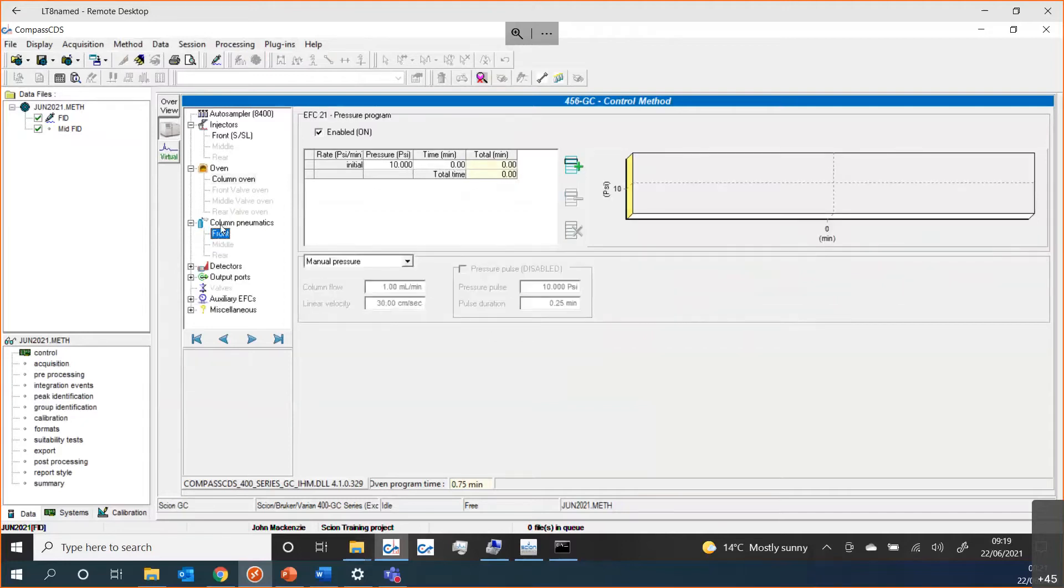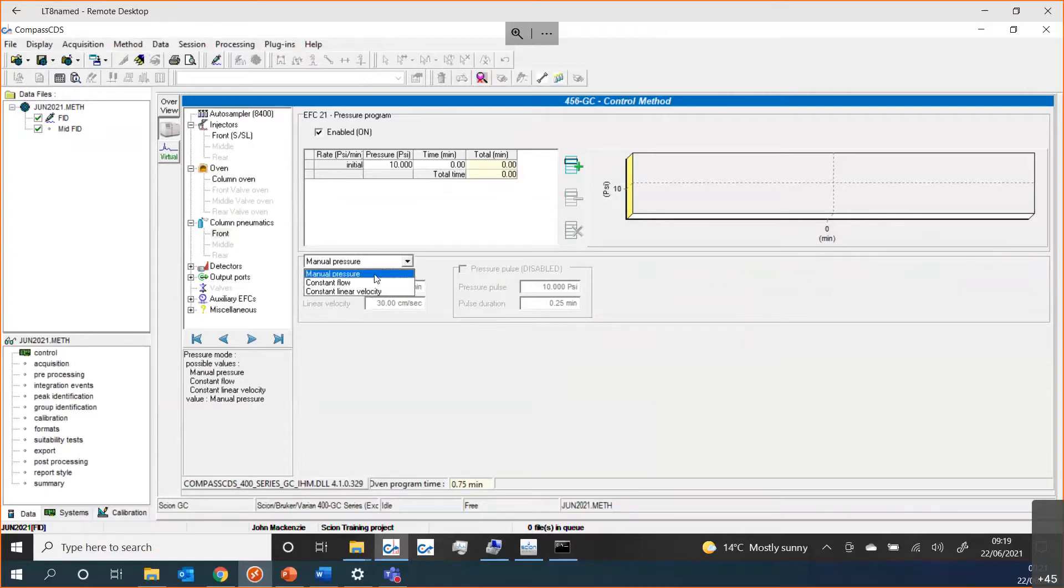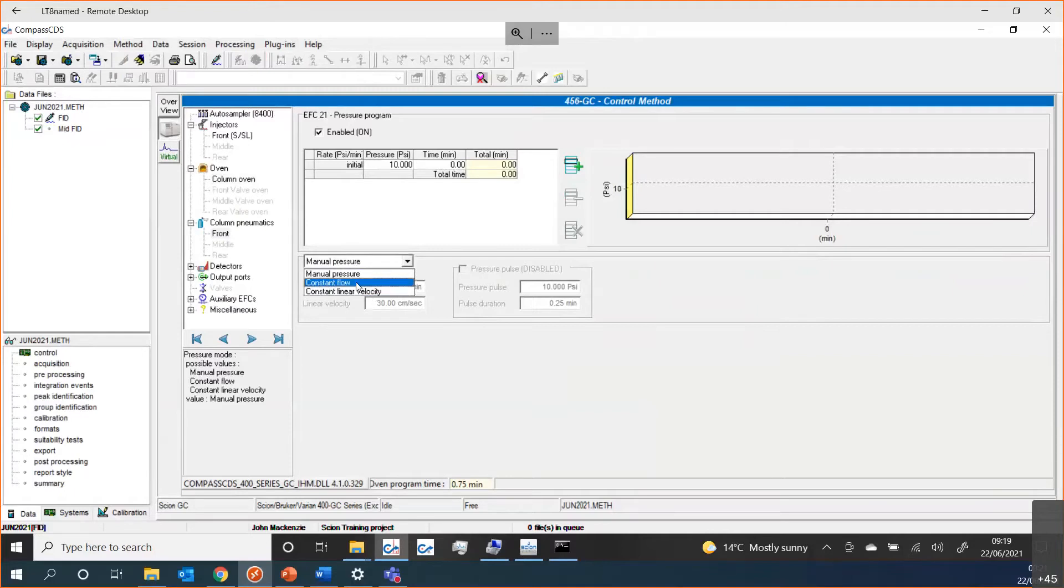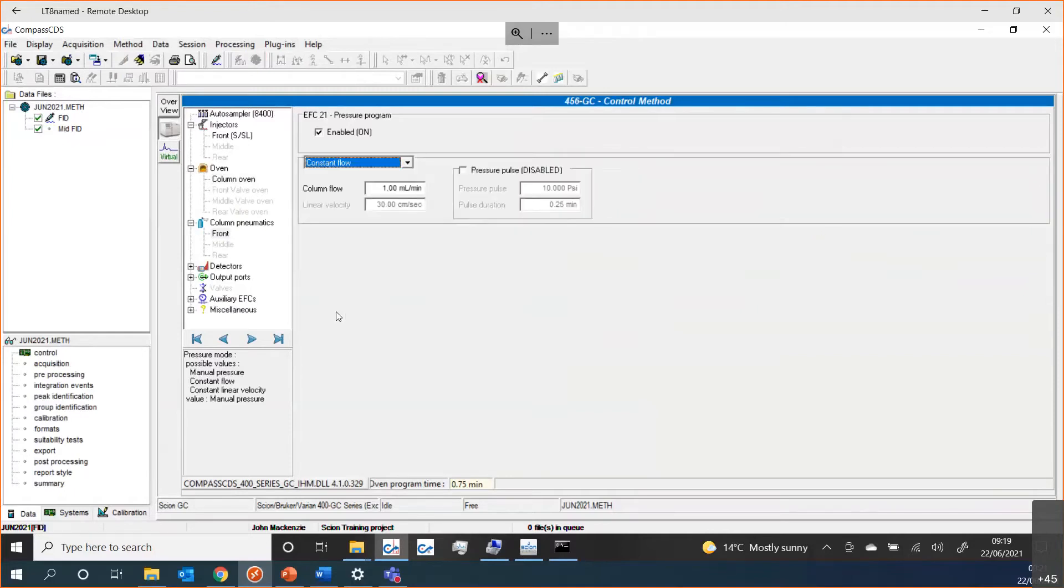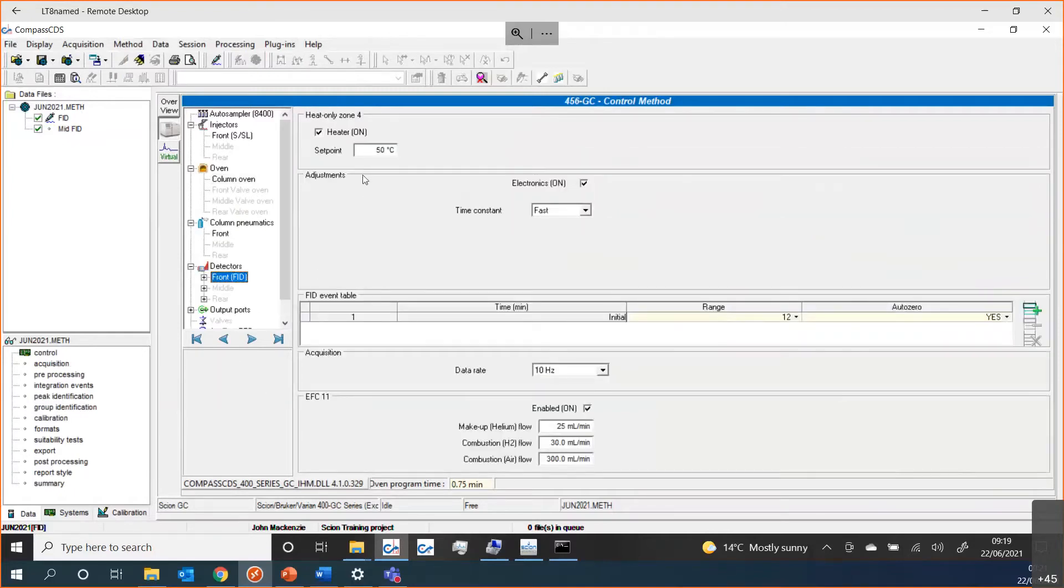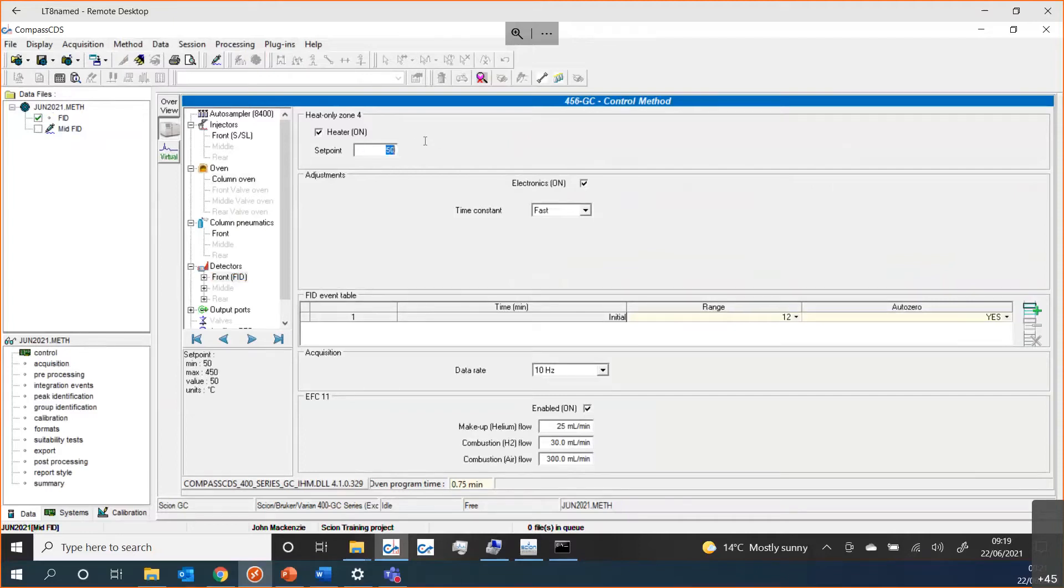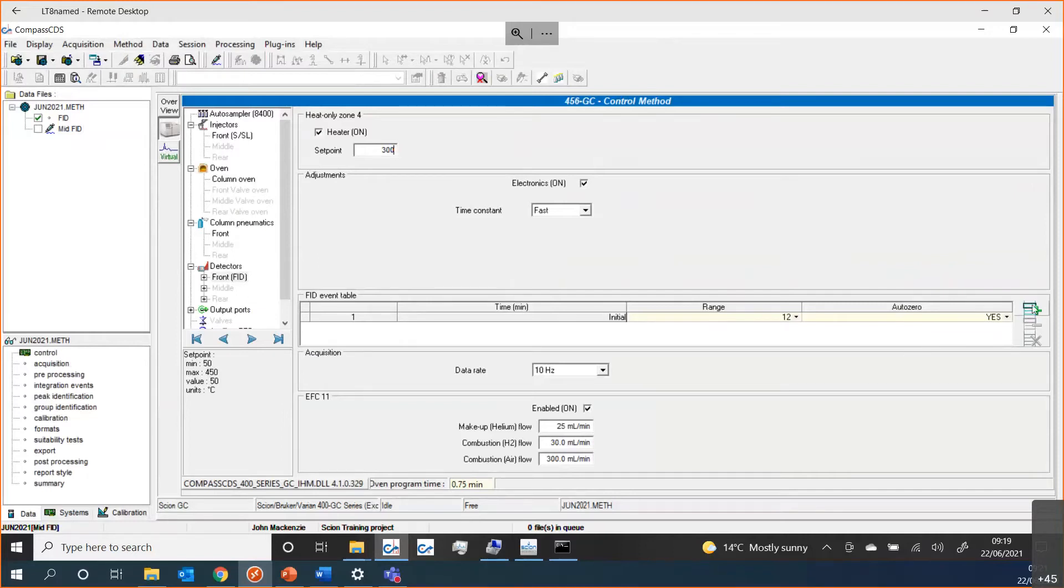In the column pneumatics, we can set what type of flow we want onto a column, whether we want to just have it pressure regulated or we want constant flow or constant linear velocity. All of these are achievable from within here. What detectors we might be doing. For today's demonstration, I'll maybe just have one detector. I could then set what the temperature was going to be, what the ranges are going to be, and if I maybe need to time program what the detector is going to do, that is also possible from within the Compass method.